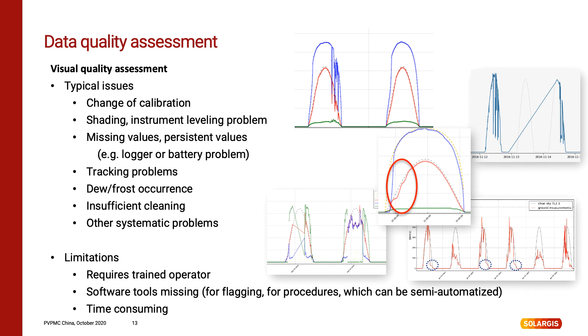Typical problems may be caused by hardware or electrical issues like wrong calibration constants or missing or persistent values due to data logger or battery problems. Other problems may have mechanical origins like instrument leveling or tracking issues. Another big source of measurement disturbance is nature, where snow, dew, frost, dirt, soiling or bird droppings occur frequently. In this case, the biggest issue is that if maintenance is not performed regularly, these defects are detected only after a significant amount of time has passed, thus reducing the quality of usable data.